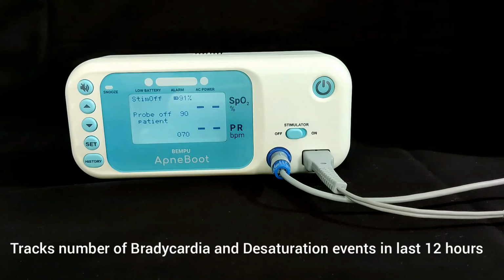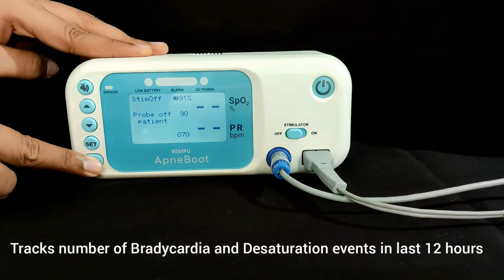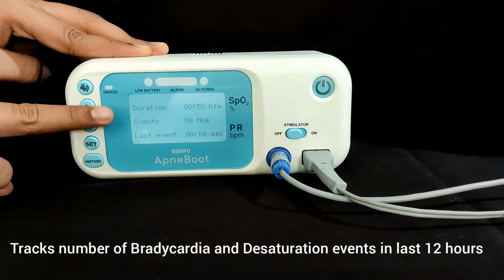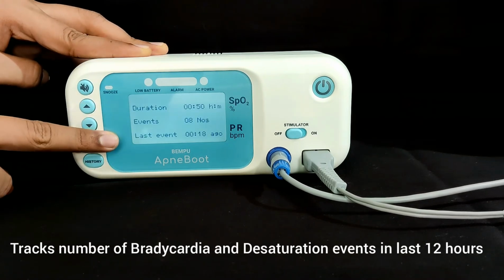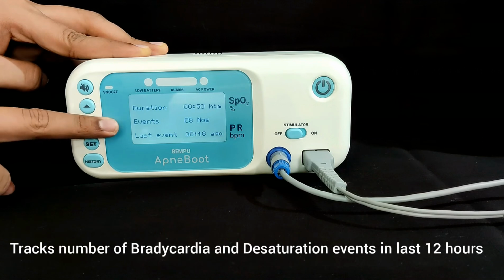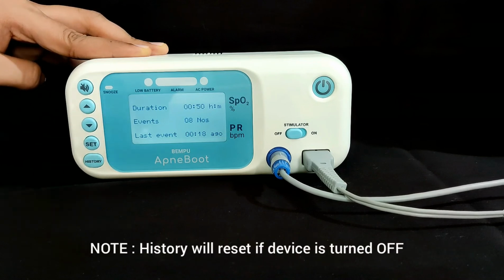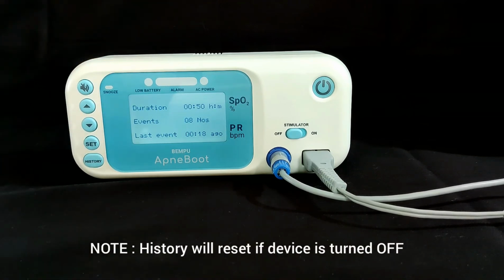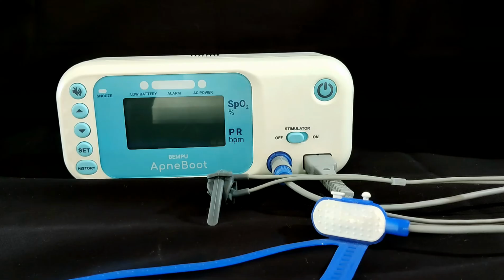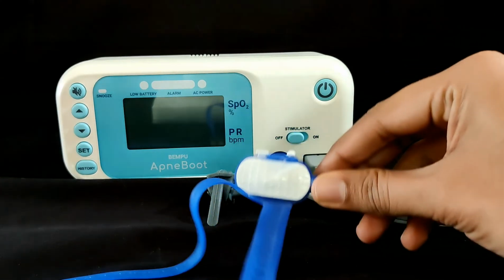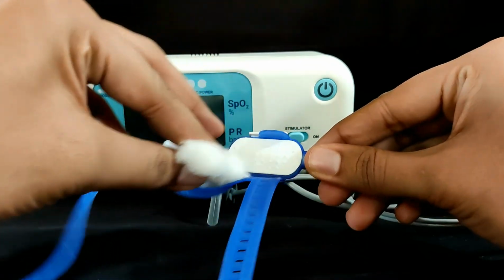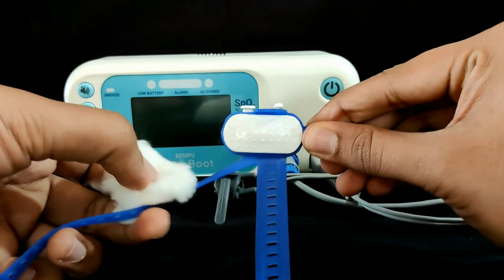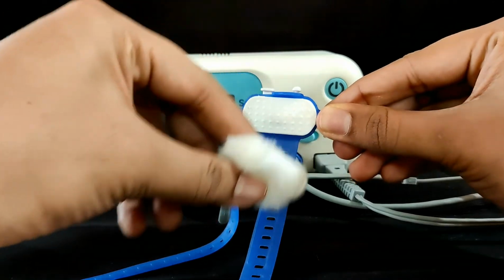The device also keeps track of the number of bradycardia and desaturation events in the last 12 hours. To check the history, press the History button. It will show the duration of history, the number of events, and when the last event occurred. Please note that the history will get reset if the device is turned off. It is important to regularly clean the device. Use a cotton swab with 70% isopropyl alcohol to wipe the pulse oximeter and foot probe before placing on a baby.